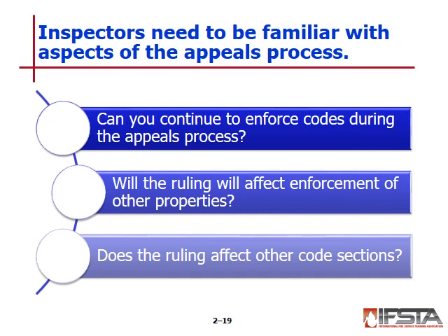Board of Appeals can use a one-time modification, referred to as a variance, binding only for a particular circumstance and not automatically applied to other situations. Approved when a situation arises that is beyond the control of the applicant and cannot be changed in a manner that meets the requirements of the code. An alternate, less efficient, option may be proposed and installed. A decision to grant a variance may be cause for concern because other applicants may expect to receive similar treatment, each circumstance evaluated separately.